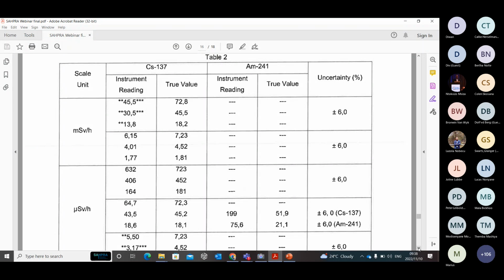Okay, so as I mentioned, the certificate should have measurement results, preferably in a table form. This is how the NMISA certificate will look. In the certificate, you will see the units that were used for the calibration, the source that was used, and also the measurements as they are. Then we have two sets of results, where the comparison comes in. On your right-hand side, you have a true value. The true value is the value of the dose or the ambient dose equivalent rate of the source that comes from the characterization of the source. And on your left-hand side, you will see the readings or the measurement results from the unit under test.